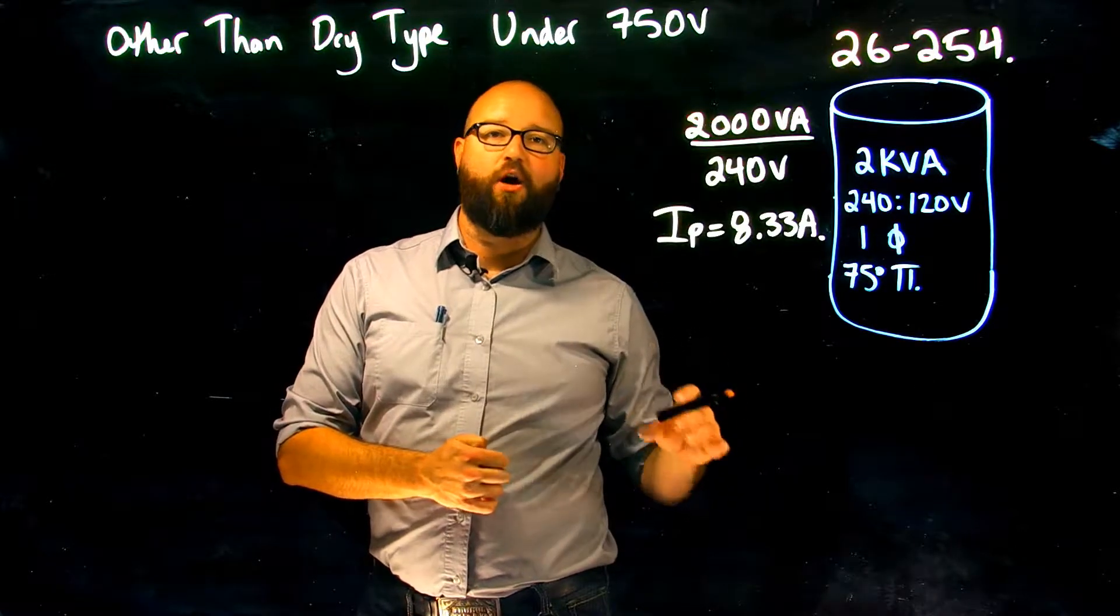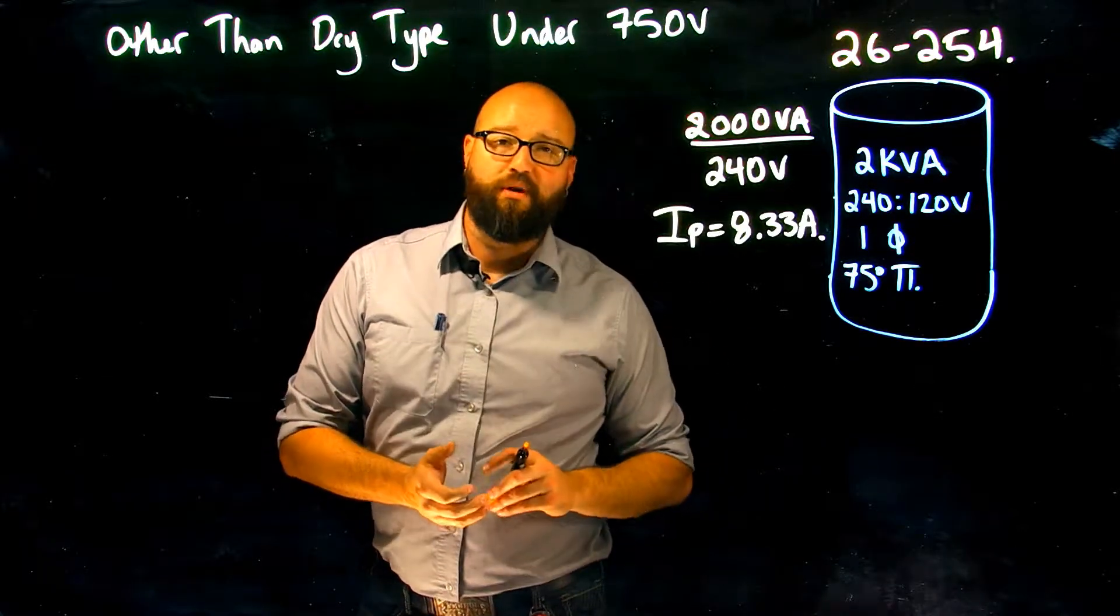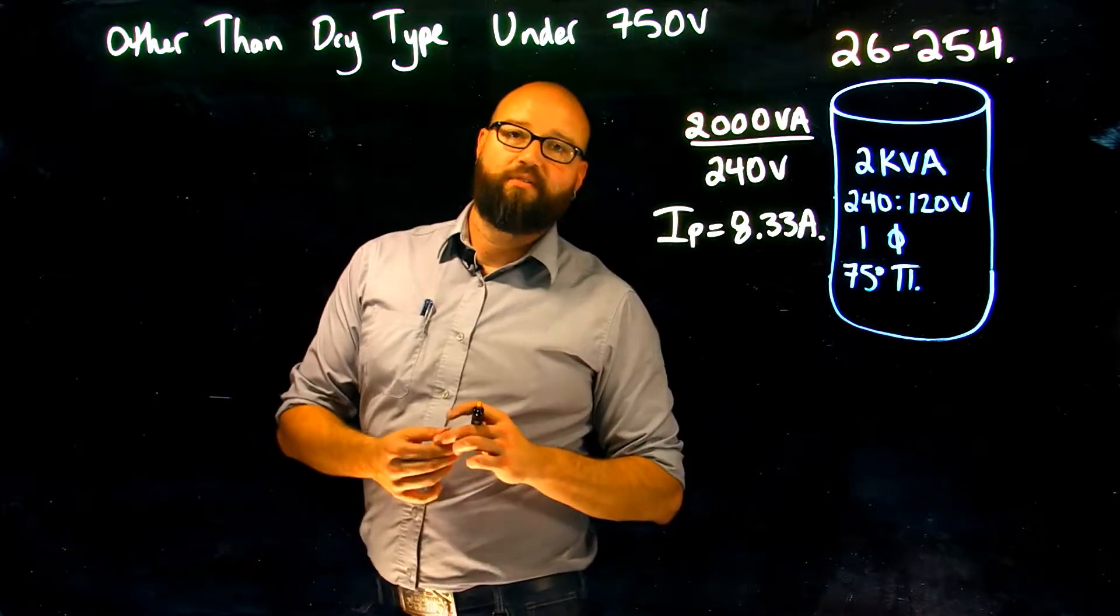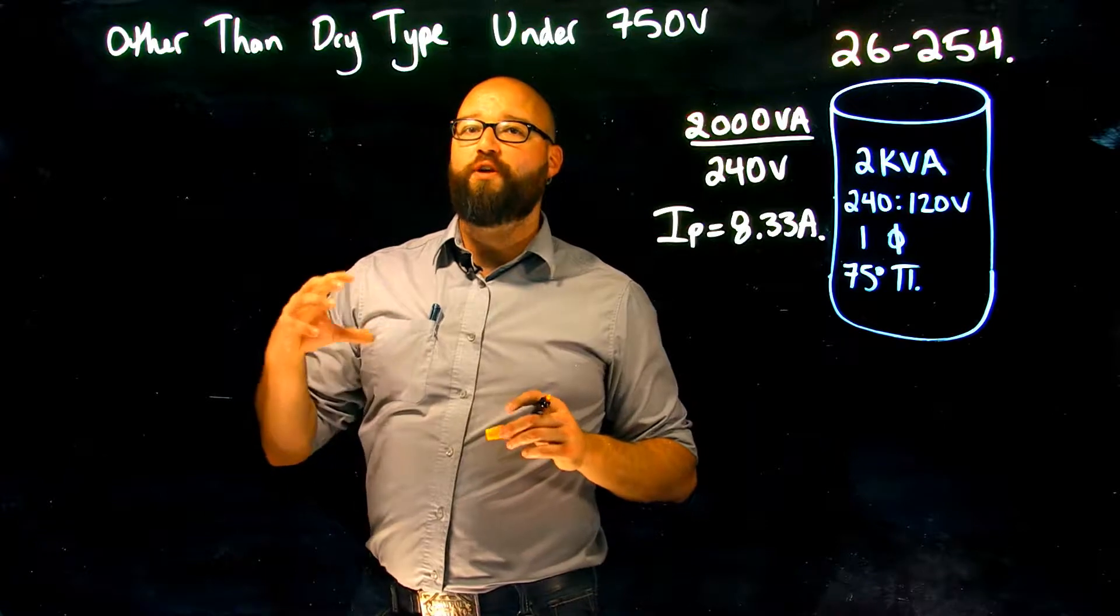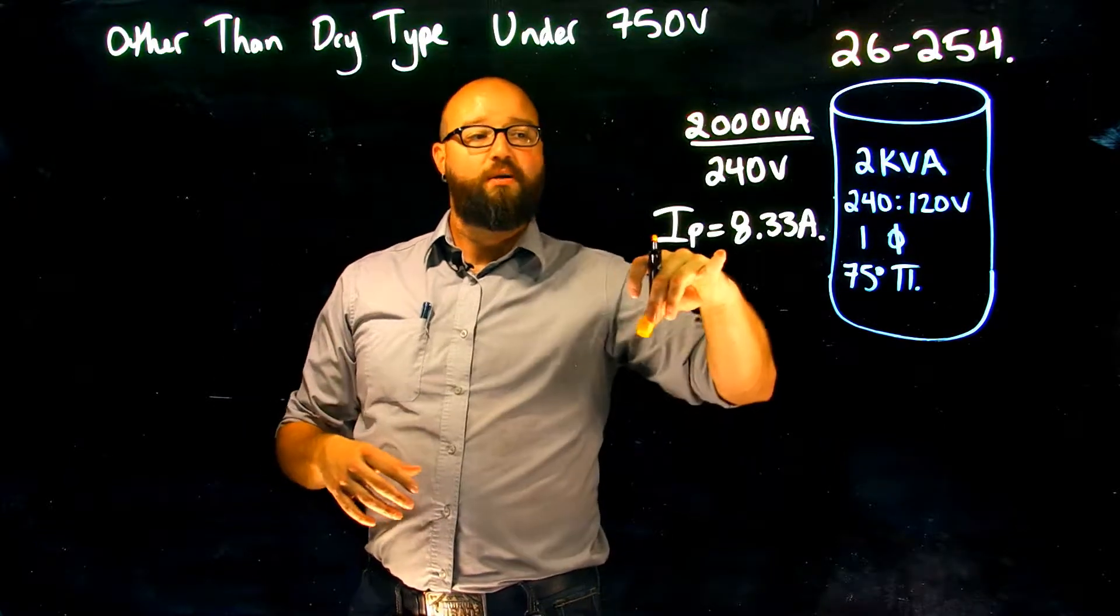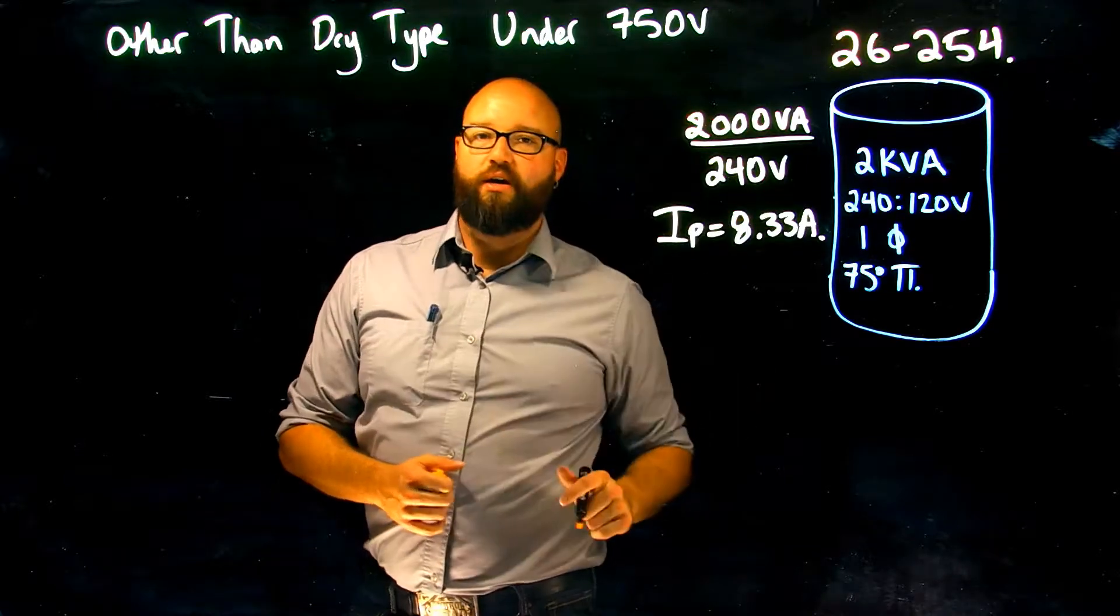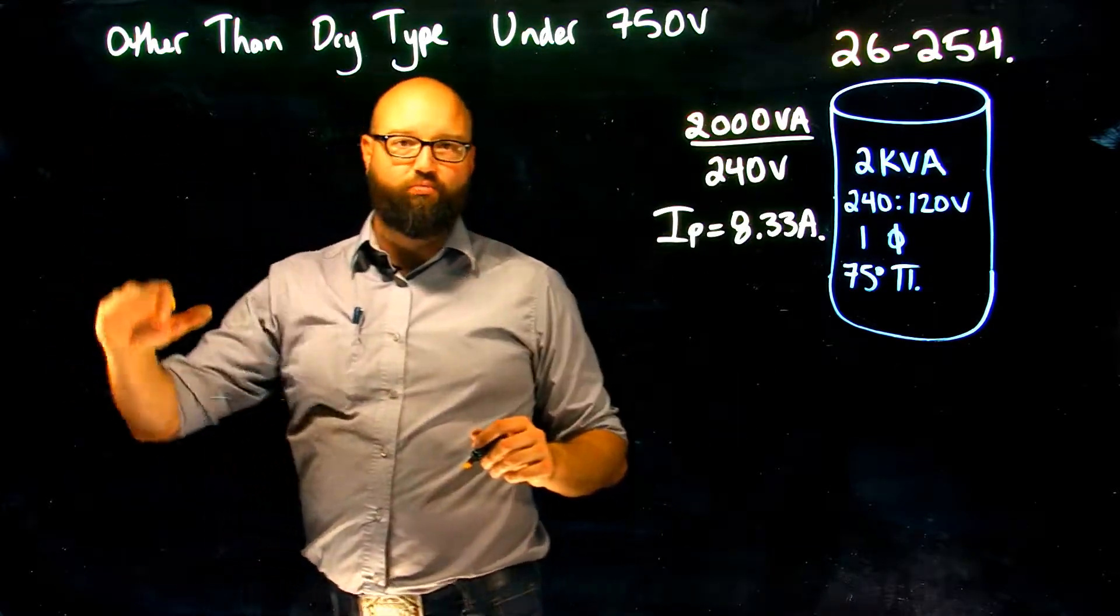But if we take a look at 2a, it actually tells us if 150 of the rated primary value is over 9 amps. So if our primary rated current is 9 amps or greater, that's where we're going to use that 150 percent. So I'm going to break this rule down into kind of a little bit of an explanation here.